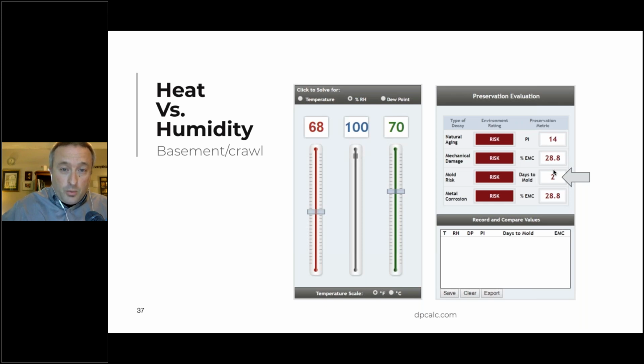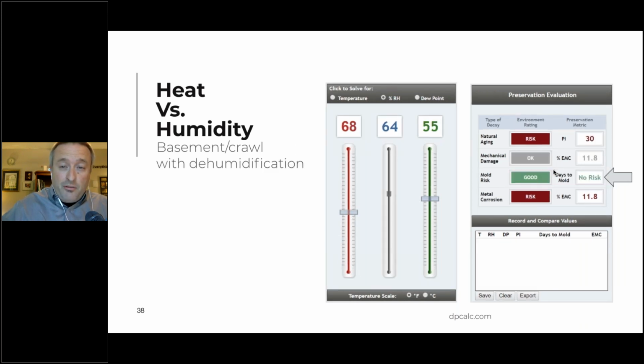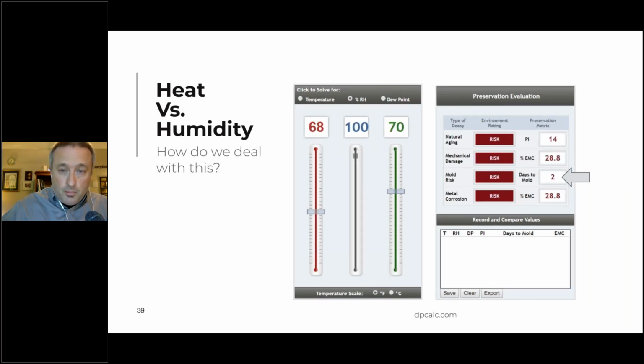So how do we deal with that? We dry it out. So if we get to that 55-degree dew point in that same 68-degree basement, now there's no risk. So you need to be able to manage the humidity of the entire house to be able to do this well. And there's lots of crawl spaces out there, just nasty, nasty, nasty. And plenty of basements too.